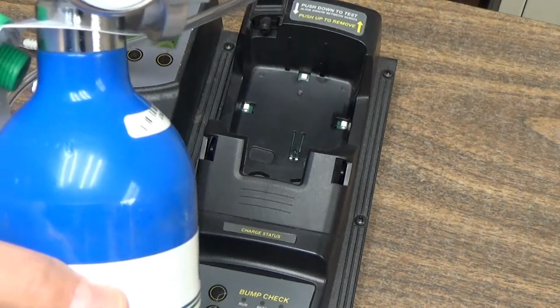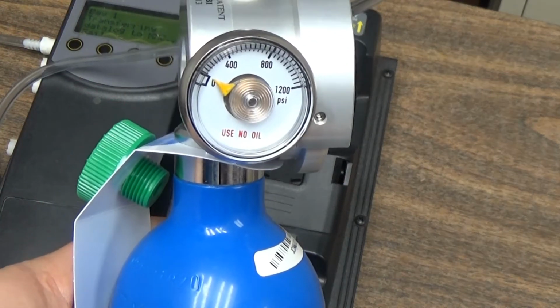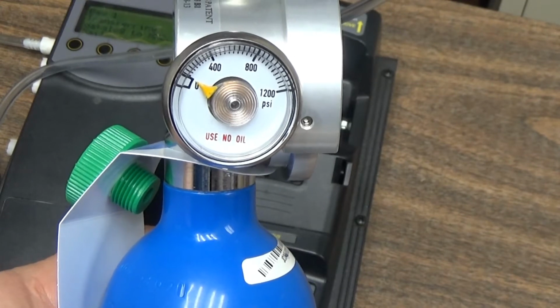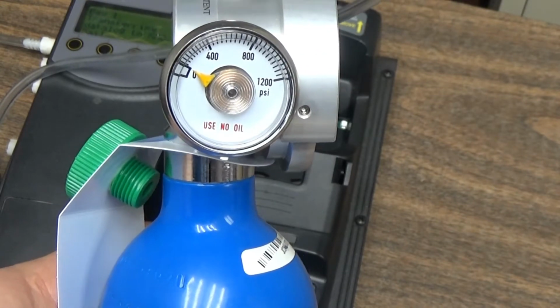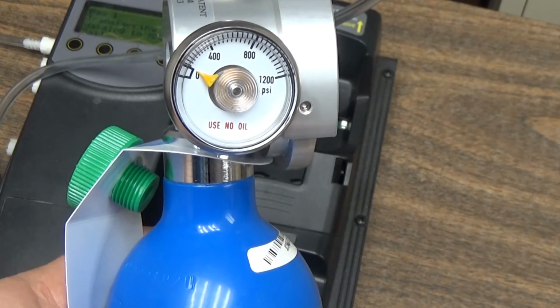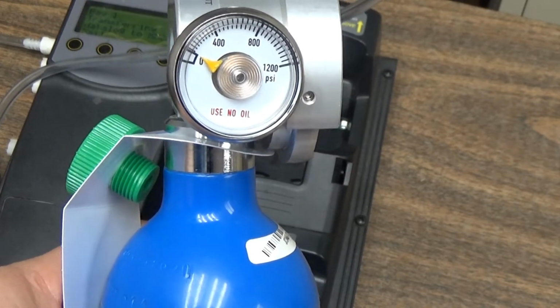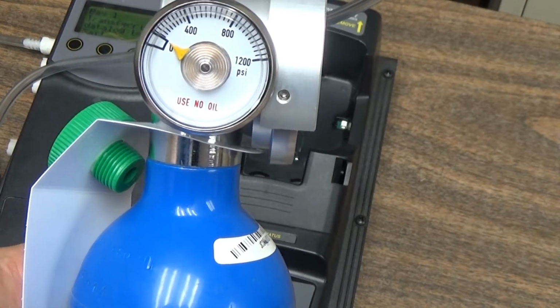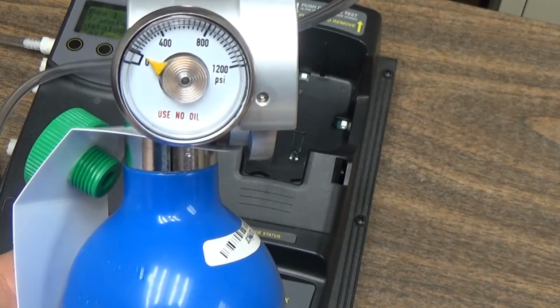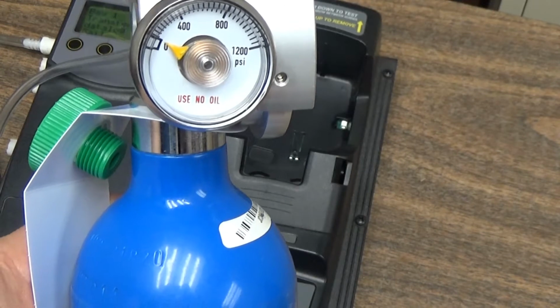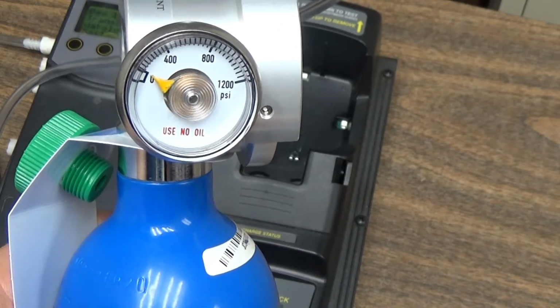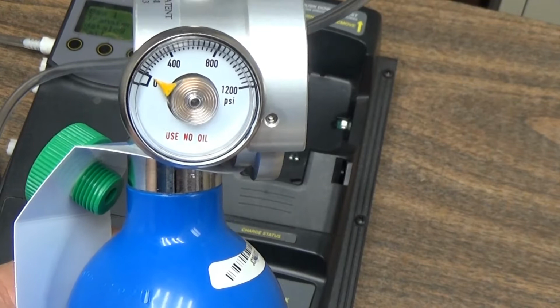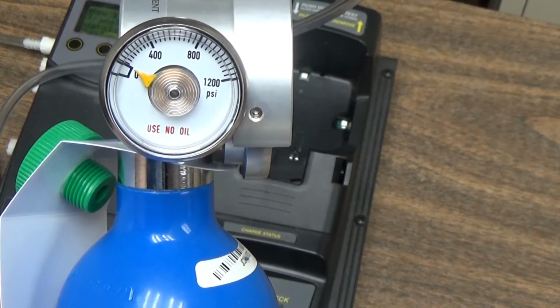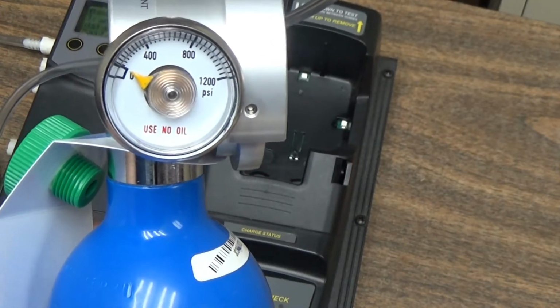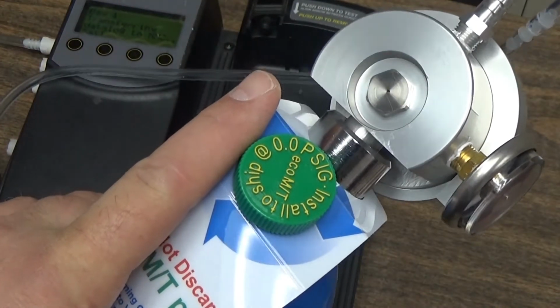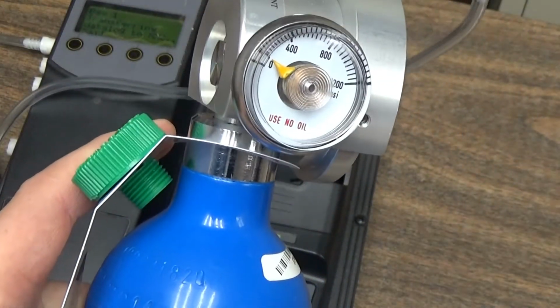One of the biggest reasons why we see sensors failing on the LEL or H2S is the capacity of the bottle. So in this case, where we had this 1 meter fail, our bottle is almost empty. It carries enough oxygen and it carries enough carbon monoxide and H2S to make the sensors read, but it doesn't have enough methane to make the LEL sensor read. So be sure that your regulator on your bottle is showing at least 200 psi. If it's showing lower than that, then go ahead and put on the empty cap and return this to the storeroom for a new one.